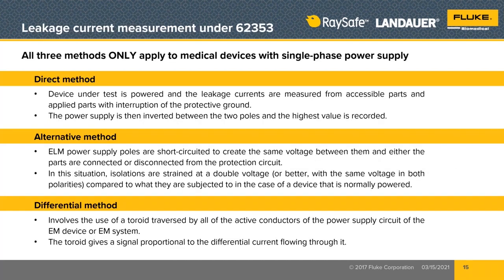So a little bit more about how we would describe each of the test methods in the IEC 62353. In the direct method, the device under test is powered, and that means you turn it on, and the leakage currents are measured from all accessible parts, all patient connections that are continuously conductive from the medical device to where they touch the patient, and the applied parts with interruption of the protective ground. That means that we are going to do all of the tests, including the single fault test, at least the one about interrupting ground, and then looking to see how much leakage current is flowing and where it's flowing in terms of the other return paths.